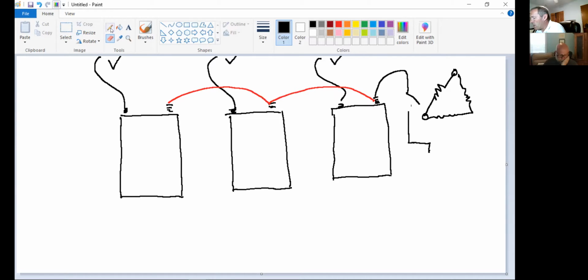I'll restate that question. When I'm energizing or de-energizing this bank with this switch closed, do I have a floating neutral? No more floating neutral - the switch is closed and it's going to ground. I closed the fourth switch, so I've grounded my floating neutral.